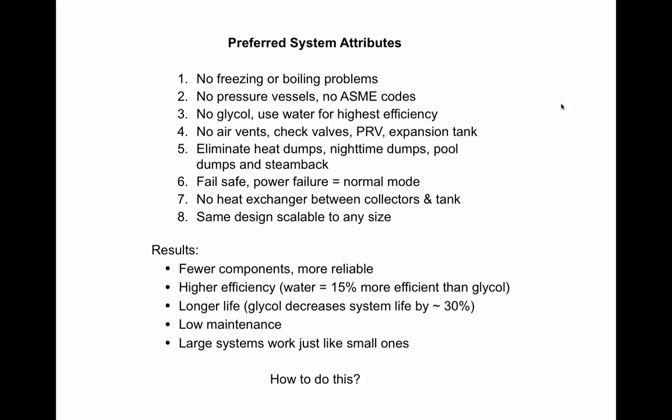We wouldn't want any boiling or freezing problems. We would like to use less expensive equipment than pressure vessels and avoid ASME codes. If we can skip glycol, that's better. Glycol costs money, it ages, it turns into acids, it eats pipes. Glycol also has a specific heat capacity in solution of about 85% that of water, so it's not as efficient as water as a heat transfer agent.